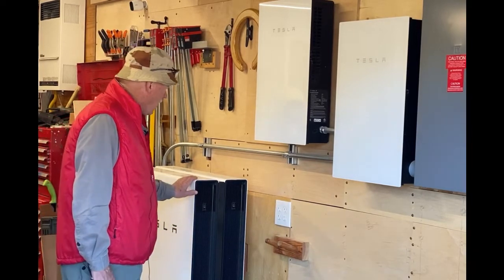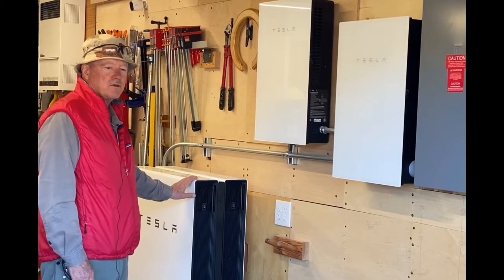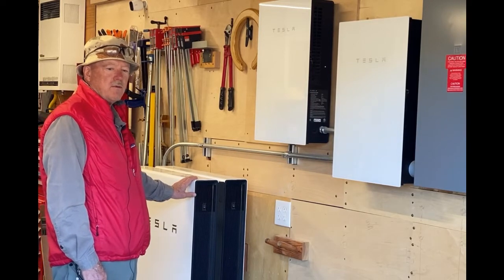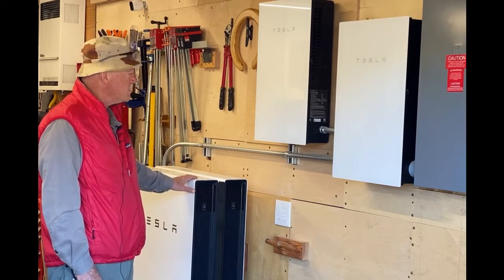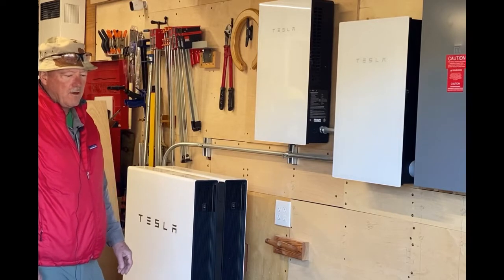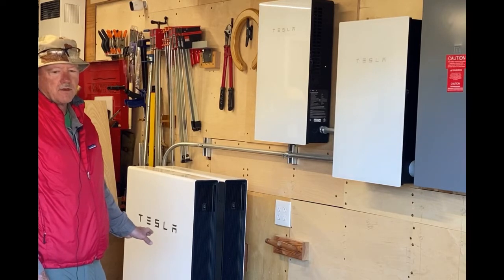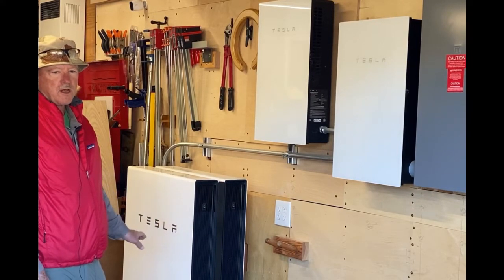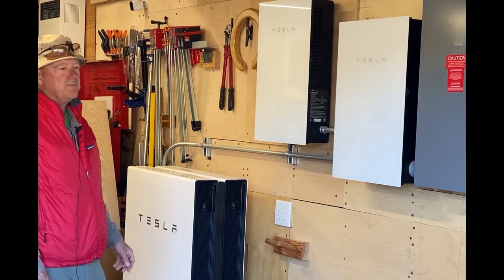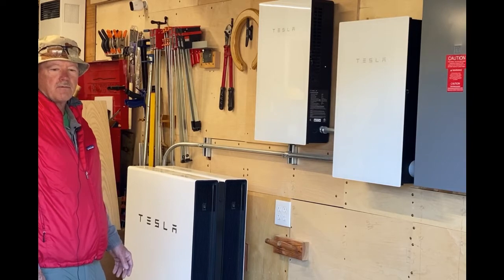The batteries we have set at a 20% reserve. The batteries even out the power usage, between day and night, so that during the day we collect energy and at night it draws from the batteries. But because one of our objectives is to have some resilience in the case of power outages, we've actually set a floor of 20% on battery discharge. So the batteries will only discharge down to 20%, and at that point they'll draw upon the grid. But that's completely up to the user to change or reprogram. We could set it to 0 to cut our power usage, but that's the choice we've made.